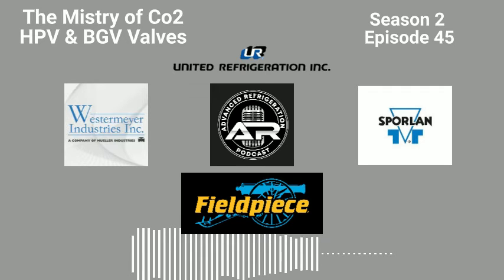So the way it does this is by venting your medium temp. By venting the flash tank into your medium temp suction, it's constantly pulling vapor off the top of the tank and venting it to the suction header. So say you have a set point of 500 pounds in the flash tank. This flash gas bypass valve is constantly pulling vapor off the top of that tank to maintain it at 500 pounds. And then your high pressure valve is constantly opening and closing, allowing pressure to come in.